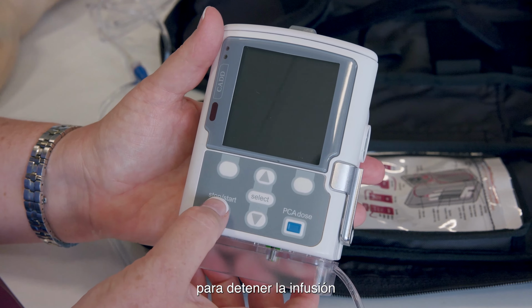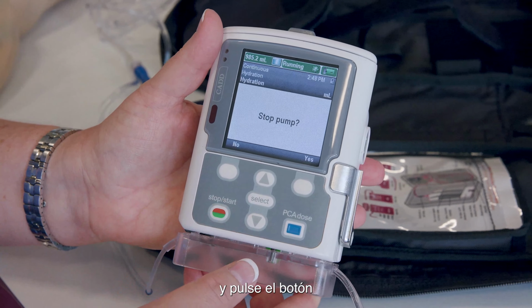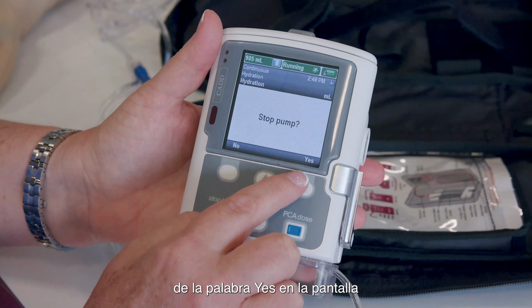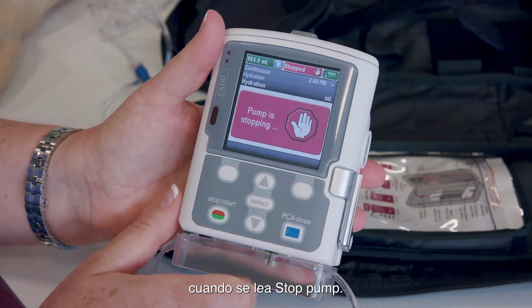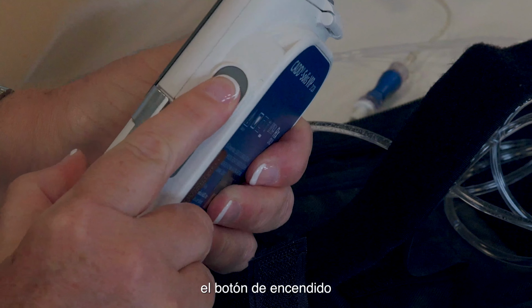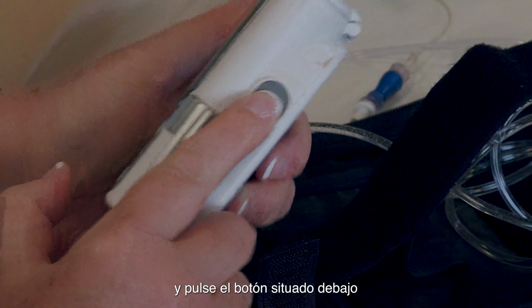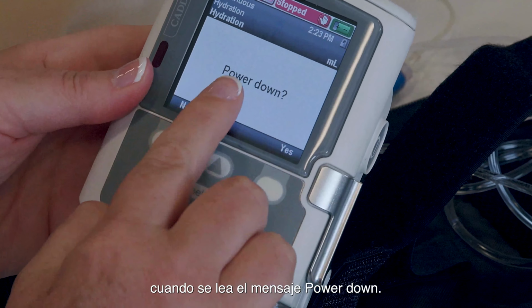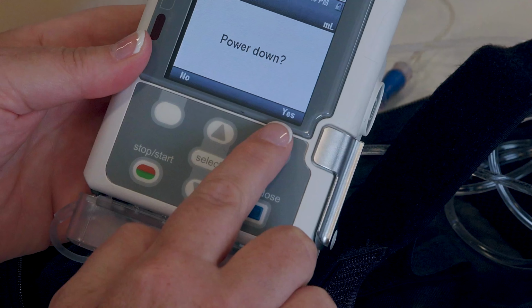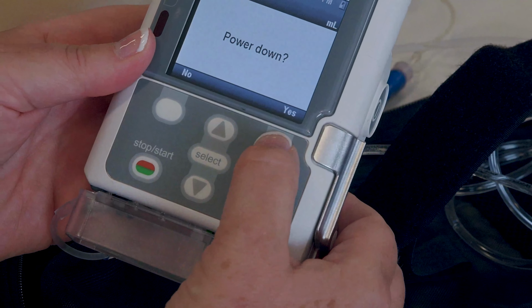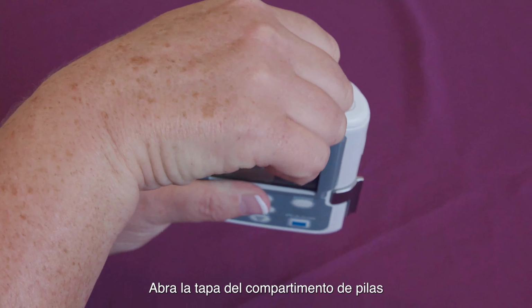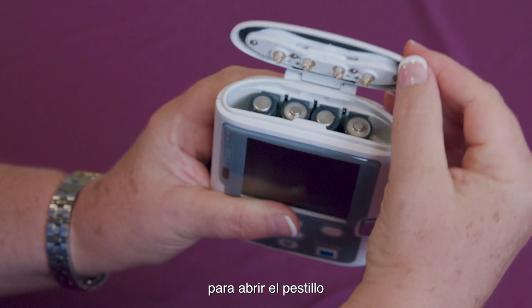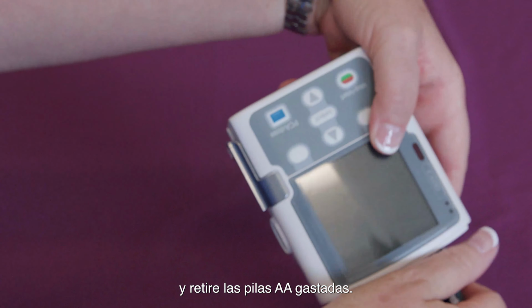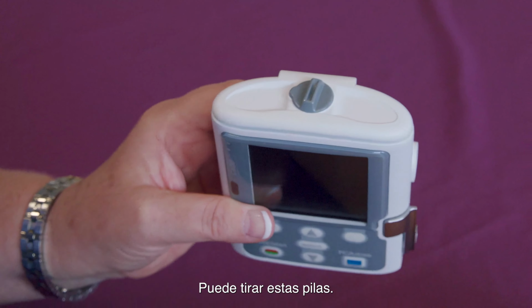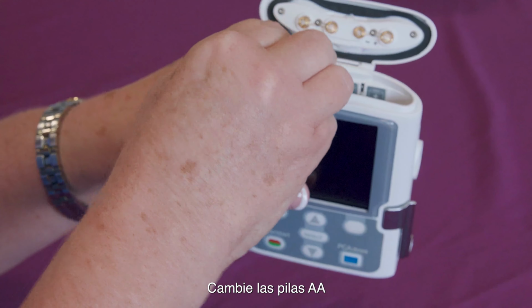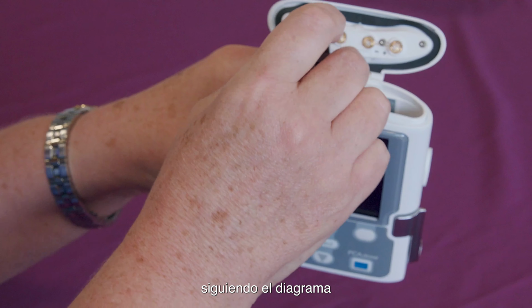You will need to push the Start-Stop button to stop your infusion and press the soft key under the word Yes on the screen when the pump reads Stop Pump. Next, press the power button on the right side of the pump and press the soft key under the word Yes on the screen when the pump reads Power Down. Open the battery door by turning the knob counterclockwise to release the latch and remove depleted AA batteries. These can be disposed. Replace the AA batteries with new batteries by following the diagram inside of the pump.